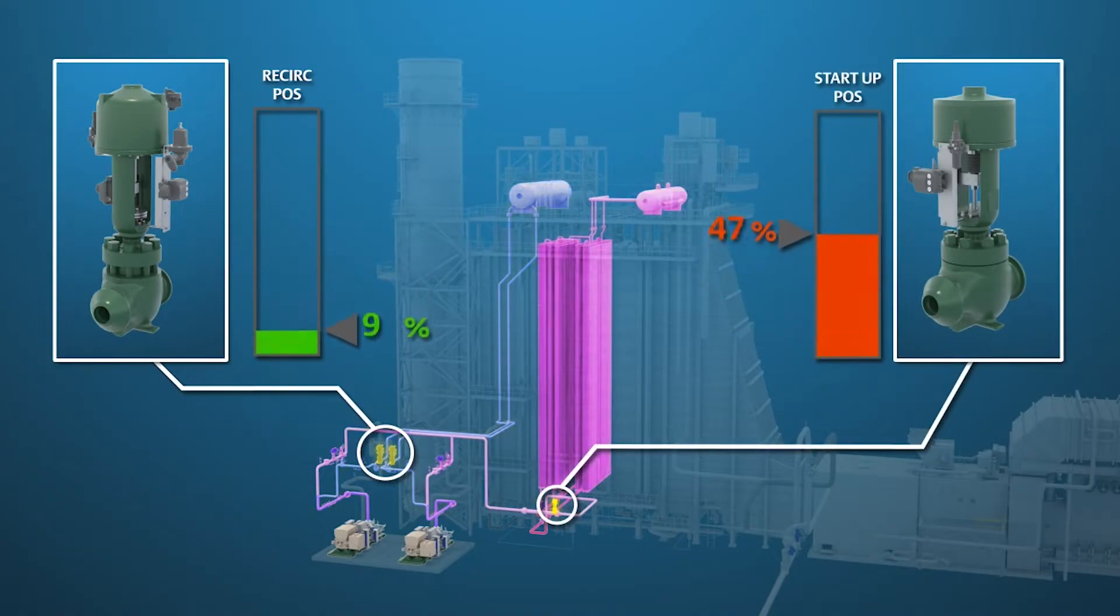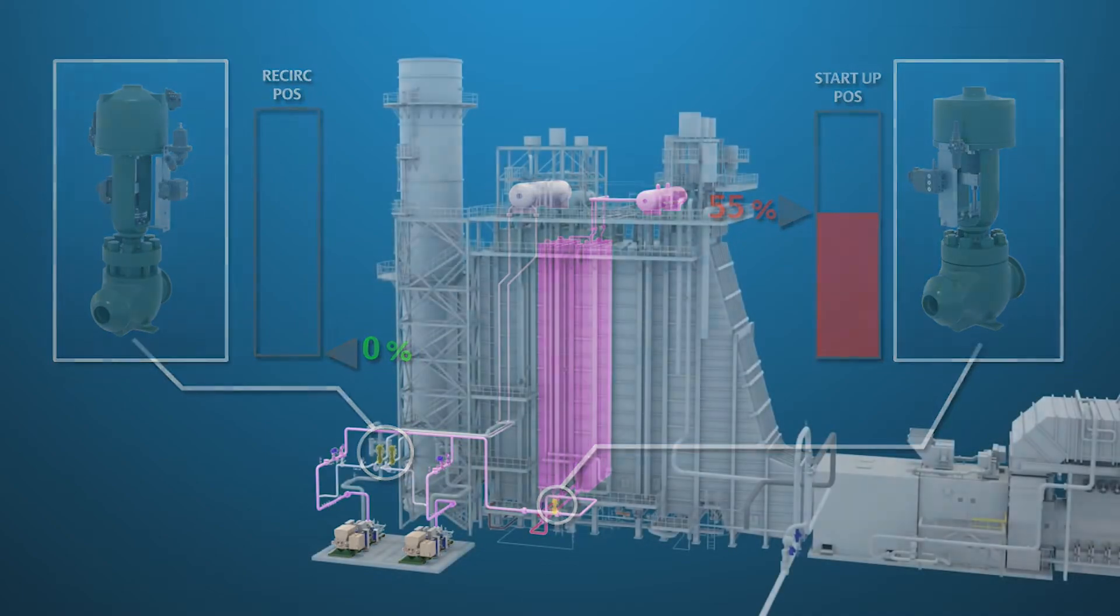If total flow is less than 30% of boiler feed water pump capacity, the recirculation valve will close proportionally as the startup valve is opened to maintain the minimum flow rate through the pump, which is the combined value of recirculation flow plus feed water flow.